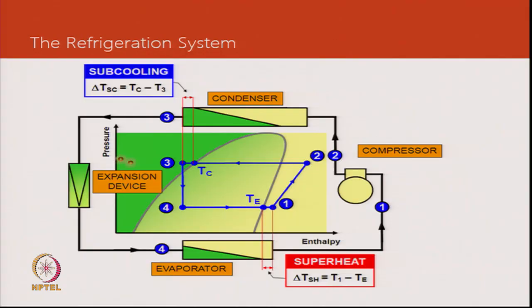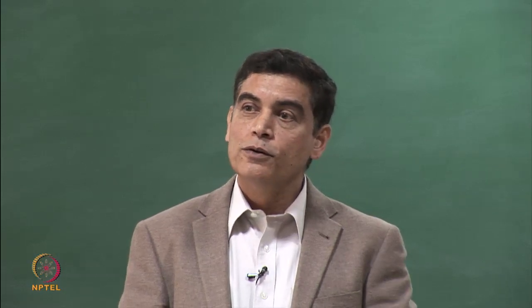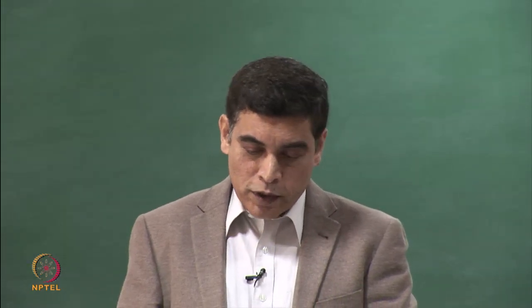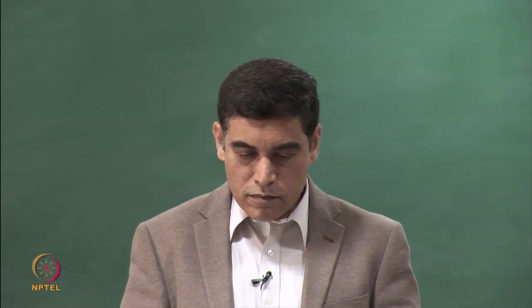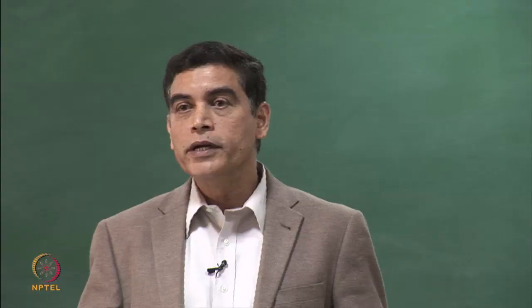Making an assumption on sub-cooling, knowing the pressure and the delta-P across the expansion valve allows us to select the expansion valve and then proceed to evaporator coil design. Additionally, we will be targeting a certain superheat in the evaporator — while not an explicit design input, we note it because we want to protect the compressor.